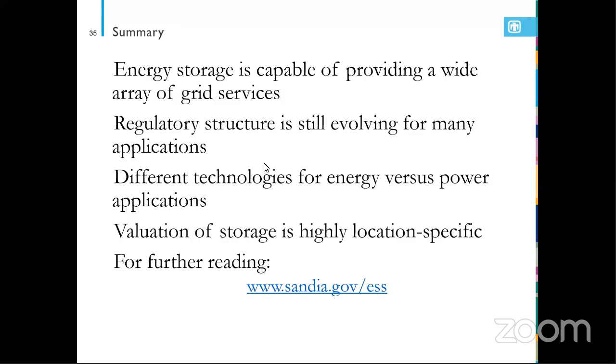They're cheaper, and they operate at a higher efficiency rate, and it's a more mature technology, so you're more sure of what you're going to get. And working with some flow battery manufacturers, some haven't delivered their products, and one of the companies that delivered their product ultimately failed in the first couple of years. And so there's more certainty, more mature technology with lithium ion and a higher performance, but there are limitations in terms of cycling.